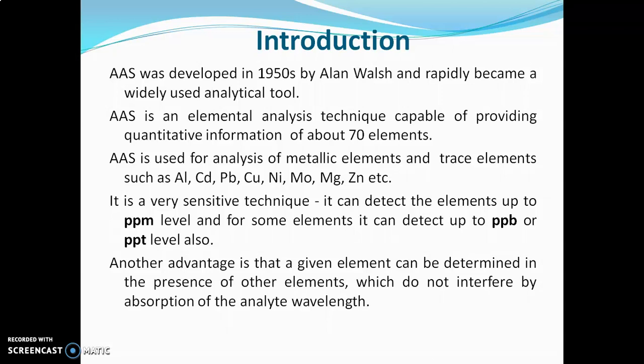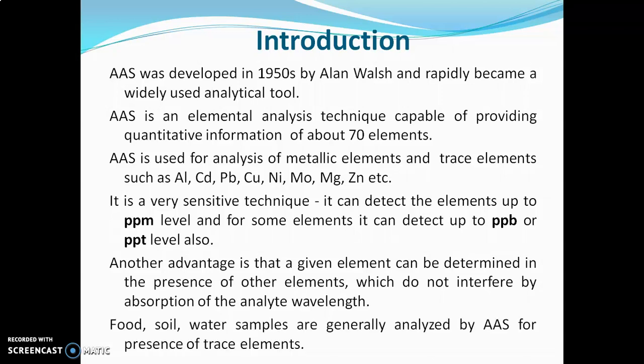Another advantage is that a given element can be determined in the presence of other elements which do not interfere by absorption of the analyte wavelength. This is where flame photometry and AAS differ: if the sample contains more than one metallic element, flame photometry will show spectral interference, and to avoid this the metallic element must be separated from the rest of the sample matrix before analysis. In AAS, such interference is not present, so there is no need for prior separation of elements, which reduces the time required.